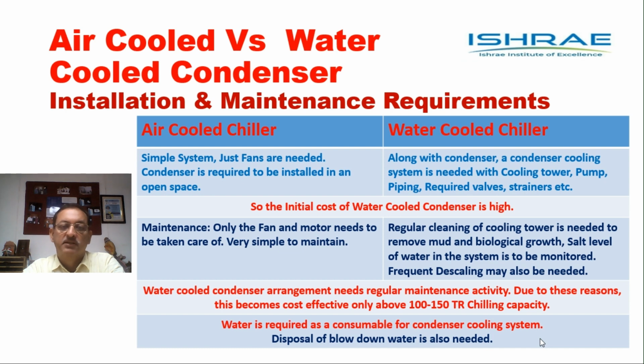Now let's talk about certain differences in installation and maintenance requirements also. We talked about advantages of water cooled condenser, water cooled chiller, as compared to air cooled chiller, but there are certain difficulties also. And let's talk about them in installation and maintenance requirements. If we recall the first picture that we had, air cooled chiller is a very simple system. All that is needed is just fans. Condenser is required to be installed in an open space, and all that you need is just fans.